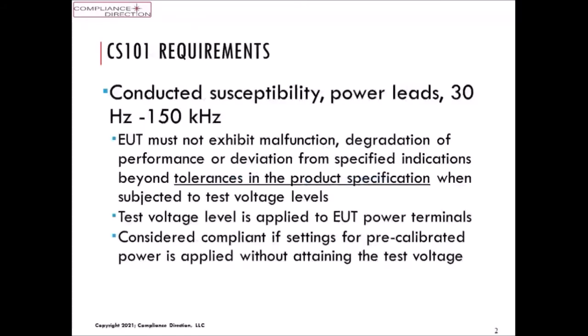there we go. As Mike indicated, this is conducted susceptibility, and the equipment shouldn't exhibit a malfunction when we apply these things at a test voltage level applied to the power terminals. It's considered compliant if the settings for a pre-calibrated power are applied without attaining the test voltage. So we're getting into a venture of two limits, a limitation on how much we try before we end up not making our test happen.